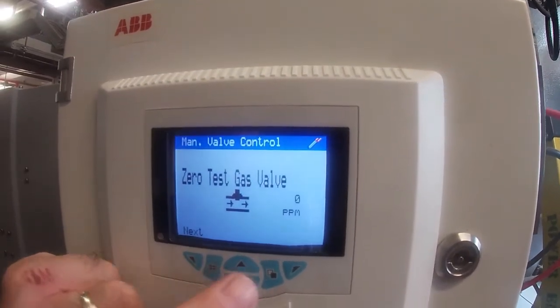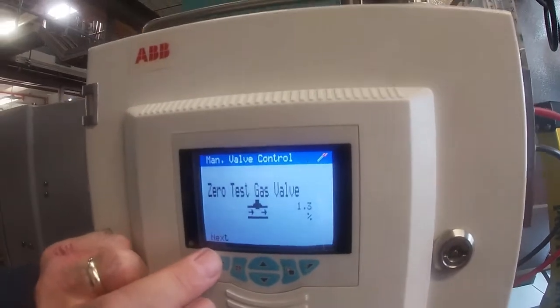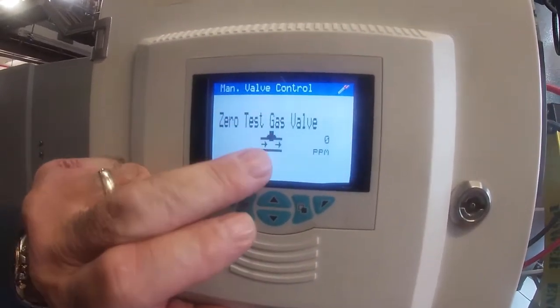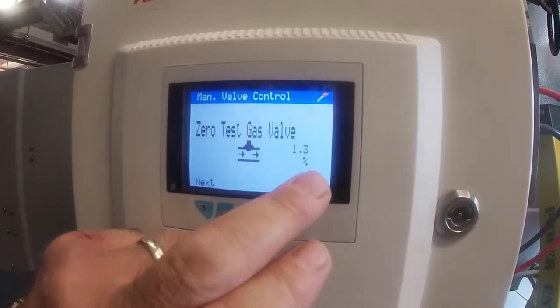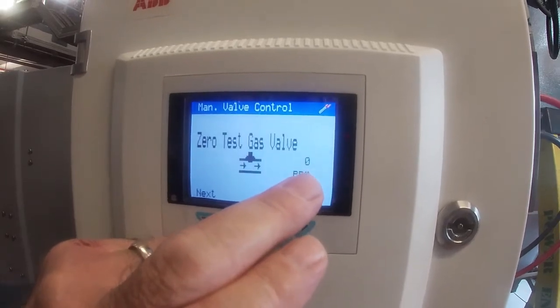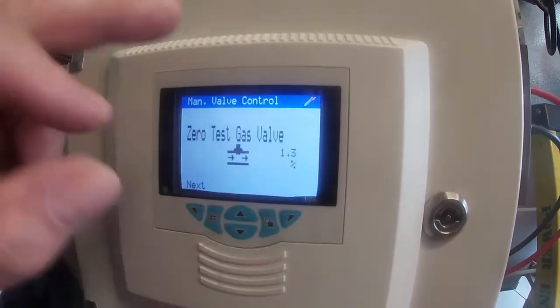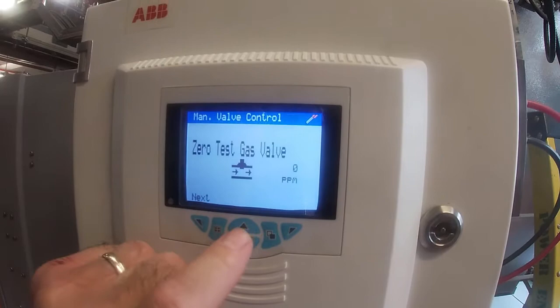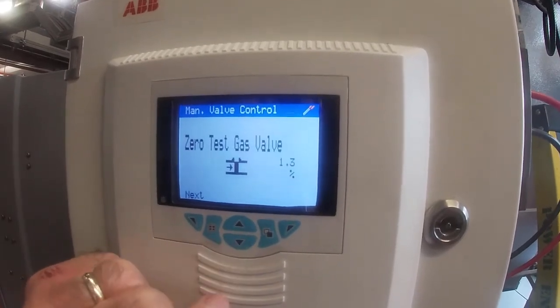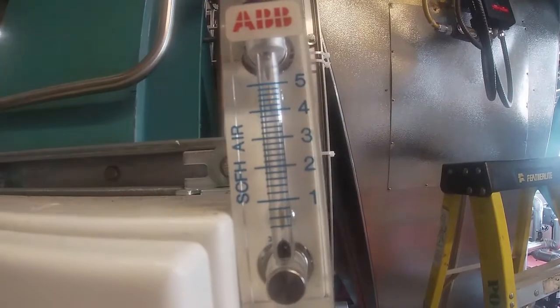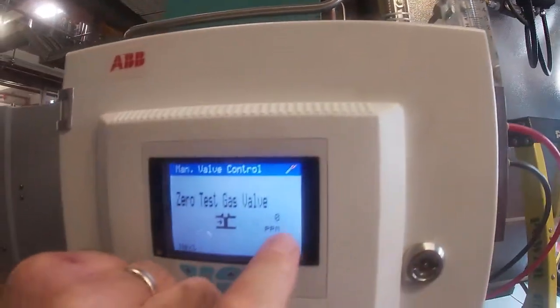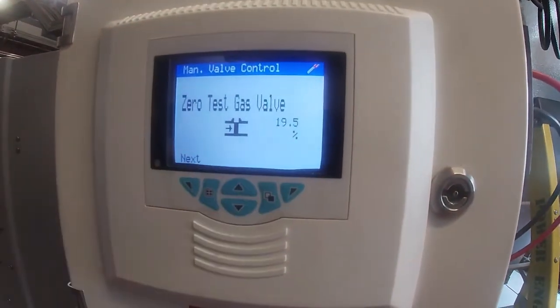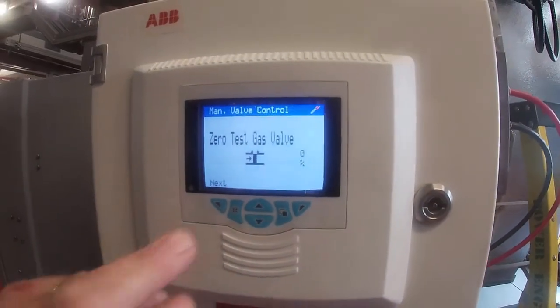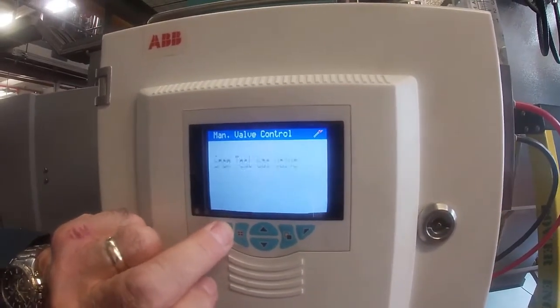So I could go next key, and what will happen is it'll automatically close the zero valve, because right now it says I've got 1.3% O2 and 0 ppm CO. They're toggling back and forth between the two. I'm going to close the valve, and you can see that the flow sample dropped down, and the O2 is on its way back up to the top. I'm going to go to the next key, and it's going to tell me about the zero gas.